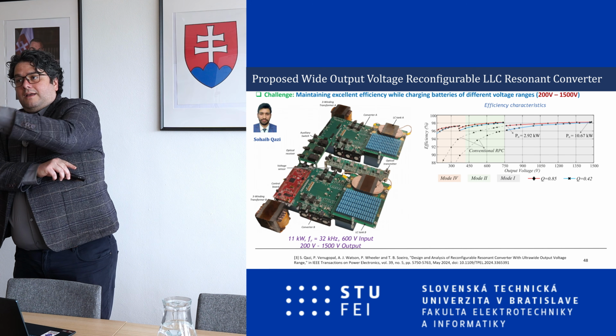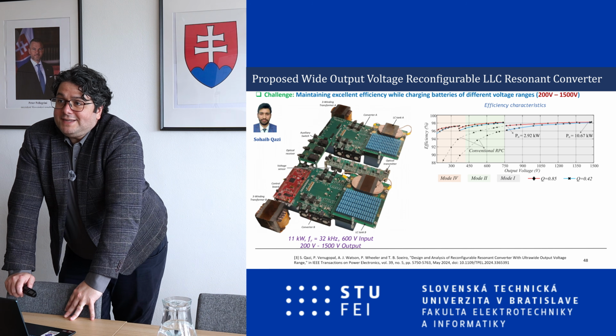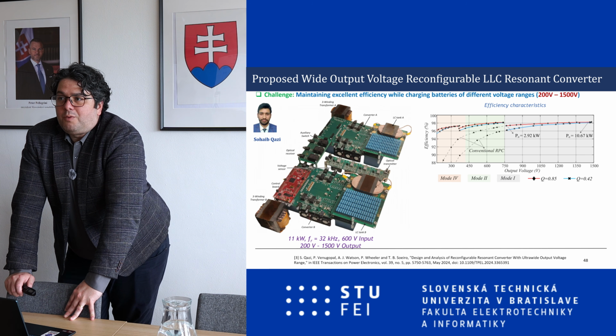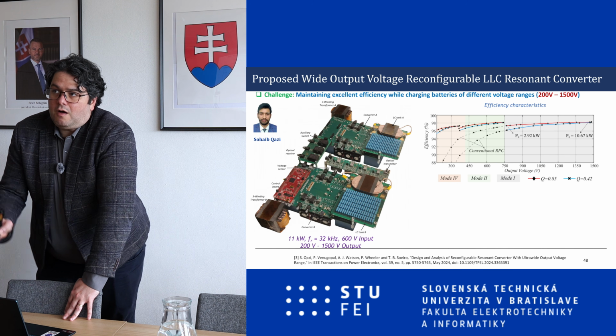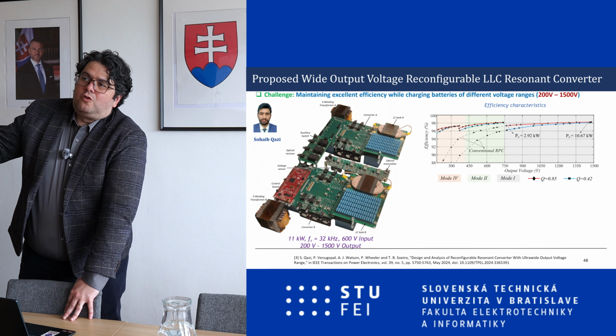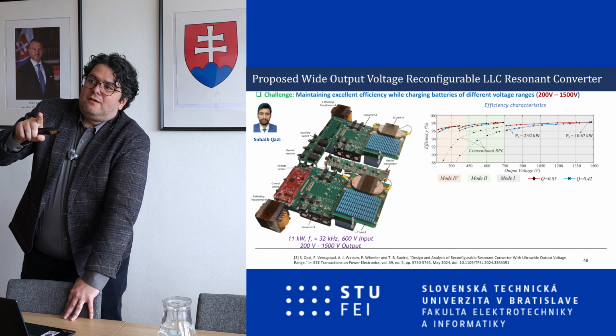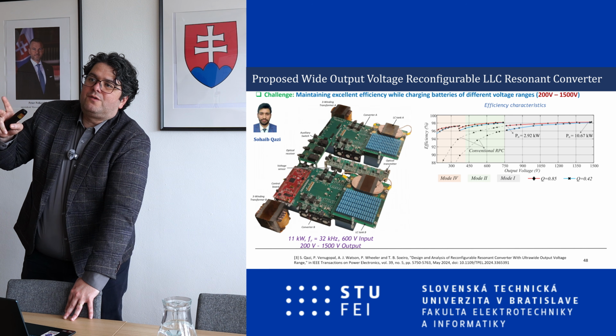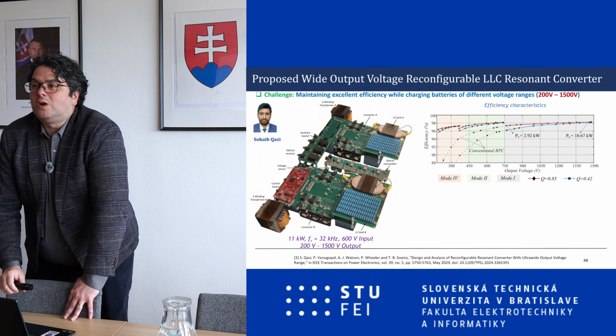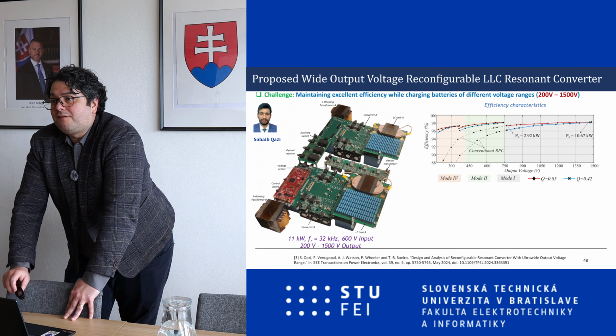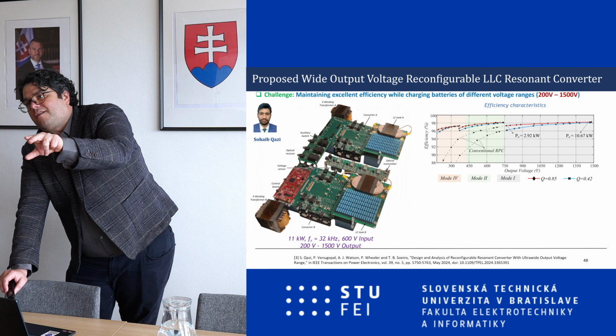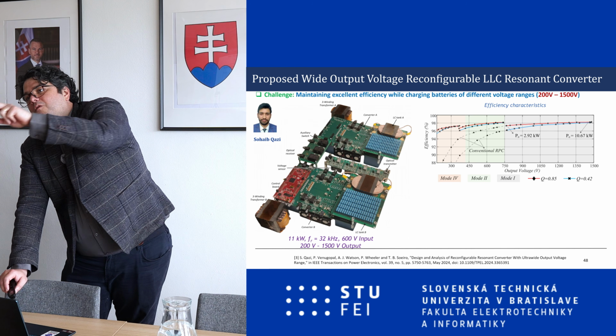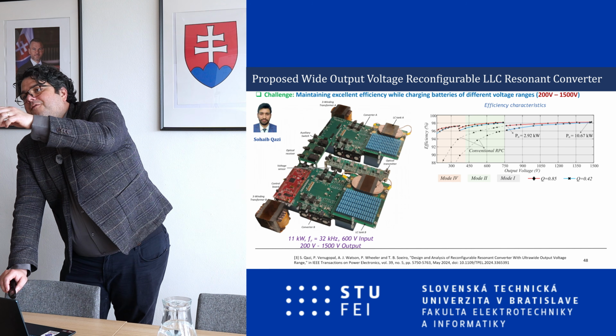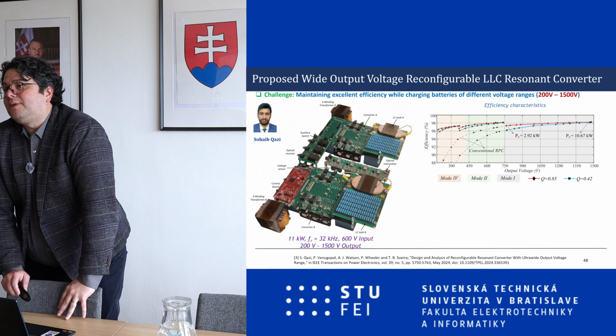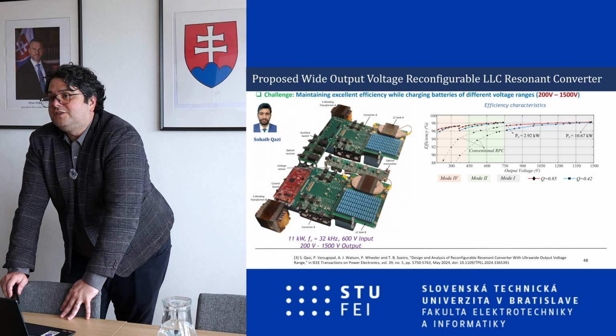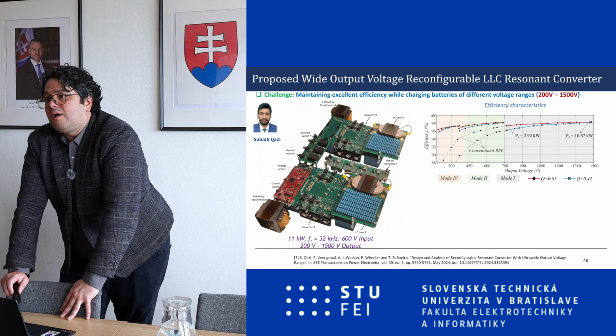What's important is that what you have there is a reset of the efficiency. In operation mode, since it's a buck-type topology, the peak efficiency is always at the highest voltage. When you drop the voltage, you also drop efficiency. But when you reset, when you change the operation or configuration, the efficiency goes back to what it was. If you use a resonant converter to charge the whole thing, you see the line there - it will be the same efficiency as the higher voltage, but for configuration at 800 volts or 400 volts, the efficiency drop is huge. That means this reconfigurability is very good.